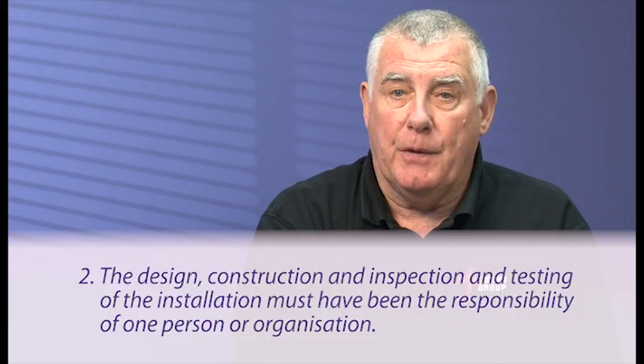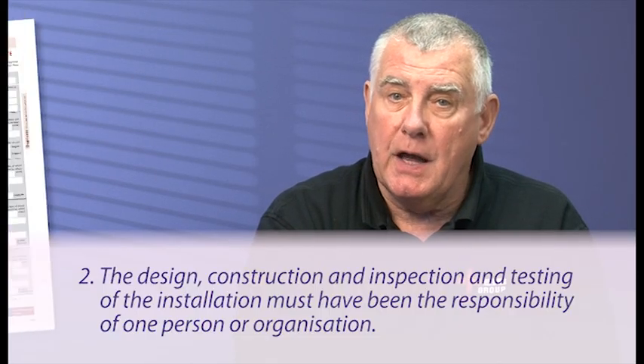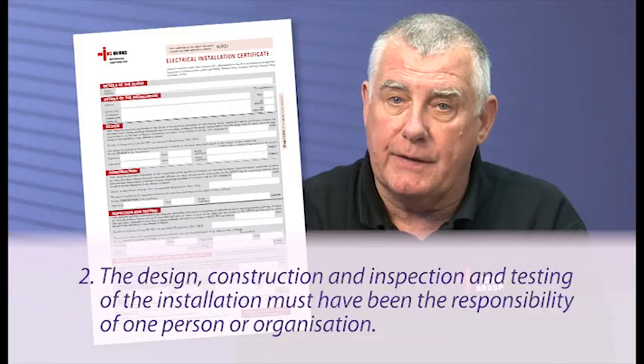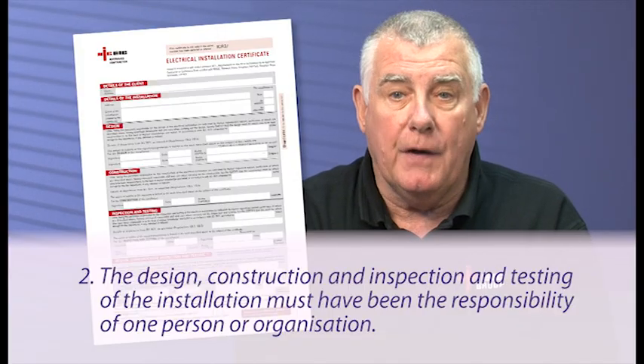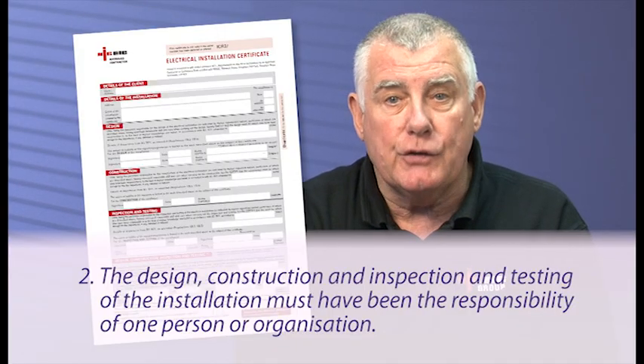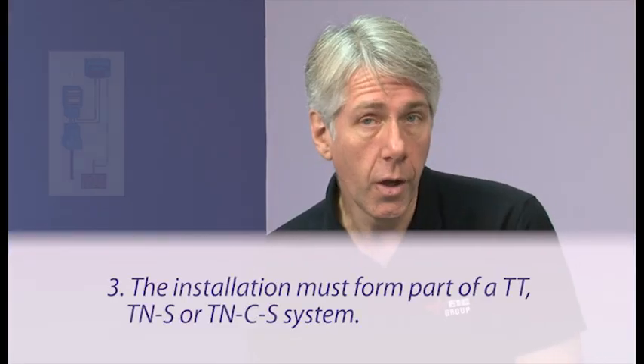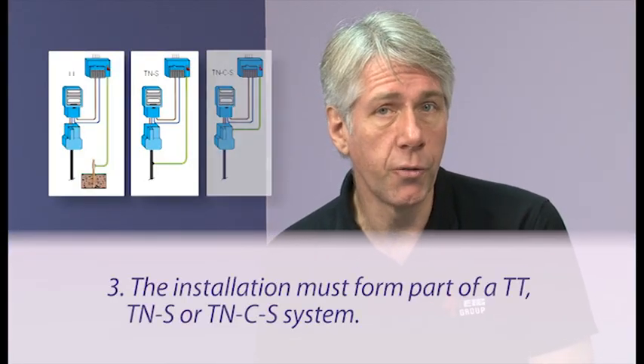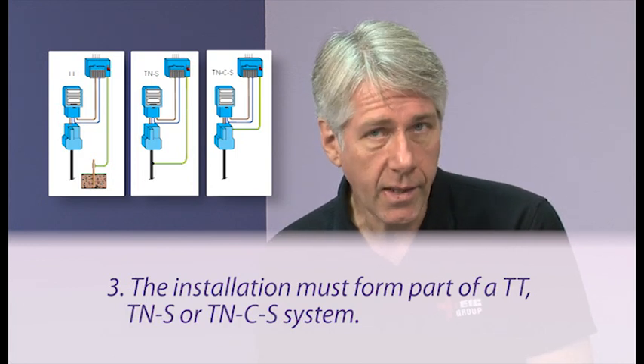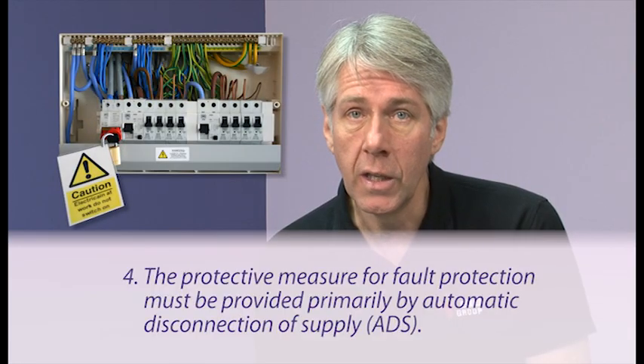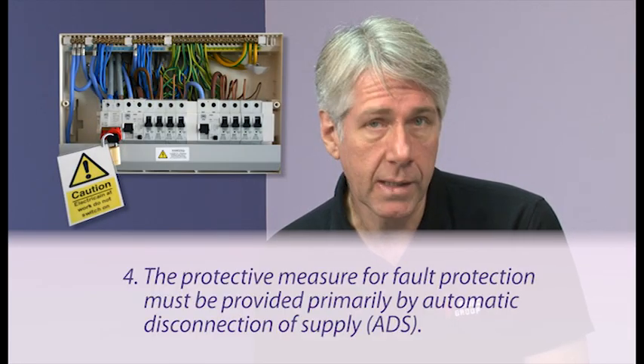If it isn't the responsibility of one person or organisation, then our full electrical installation certificate will have to be used, which provides boxes for each relevant person to sign. The third and fourth requirements are that the installation forms a part of a TT, TN-S or TN-C-S system, and that the protective measure for fault protection is provided primarily by automatic disconnection of supply, ADS. And moving on to the minor domestic electrical installation work certificate, for what types of work should this be used?